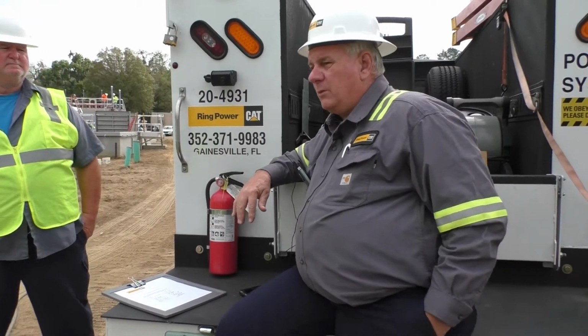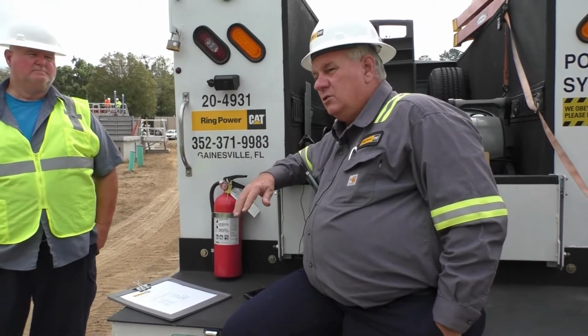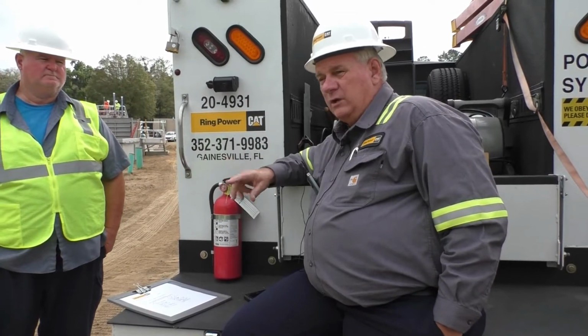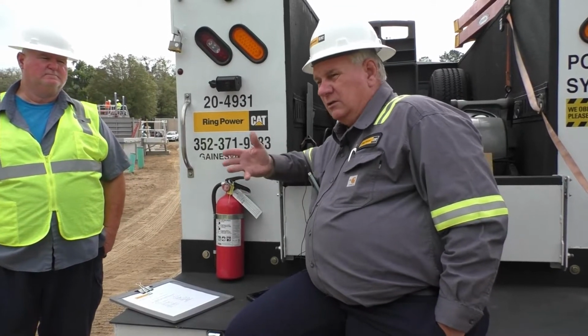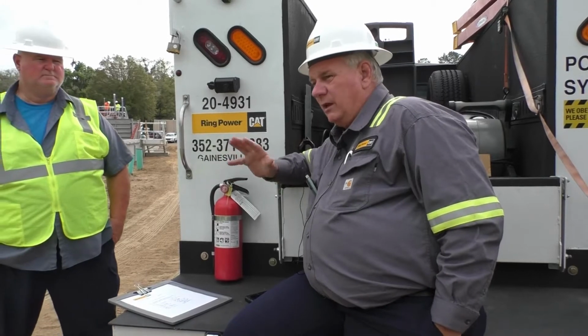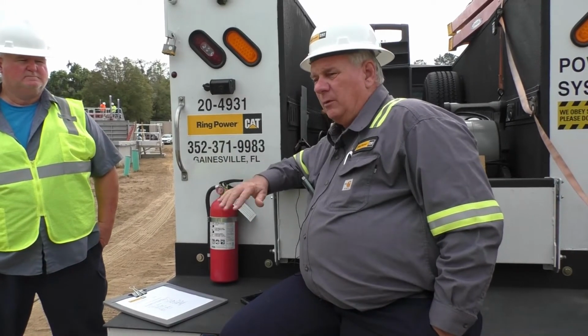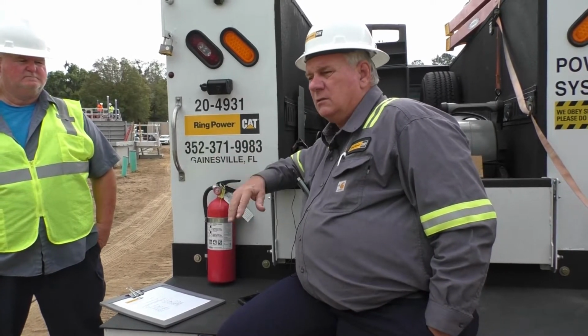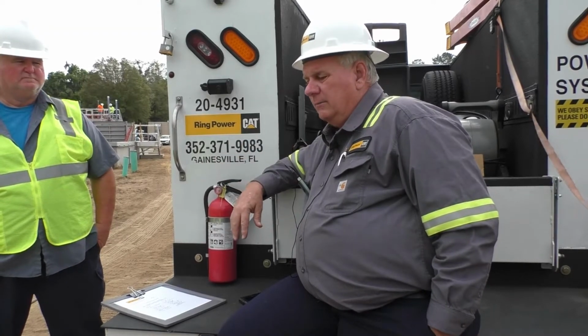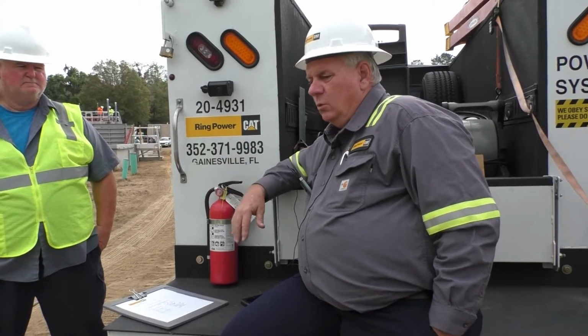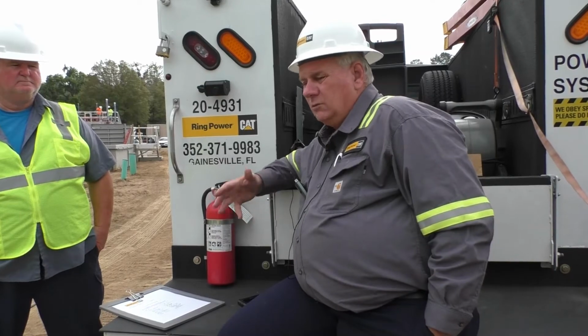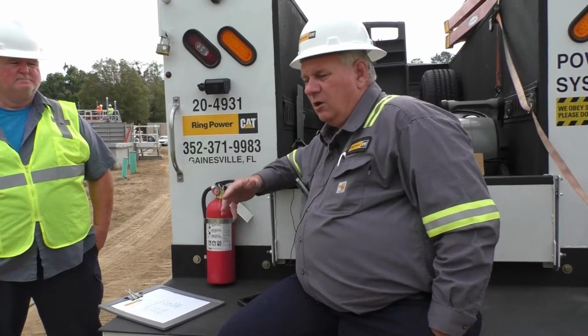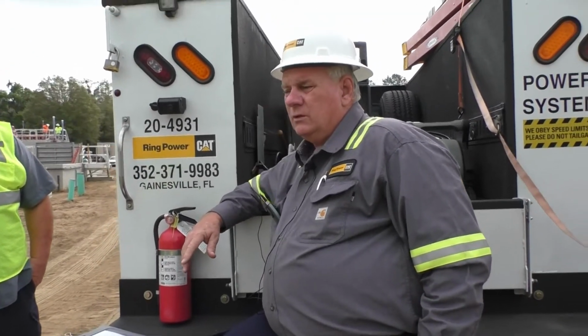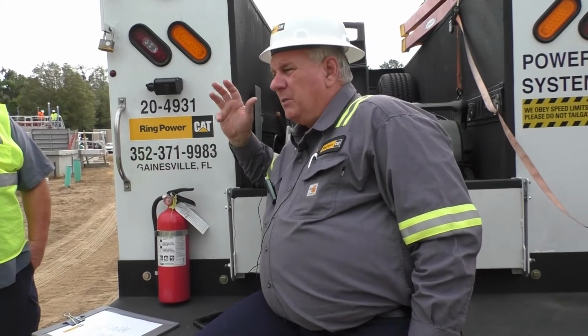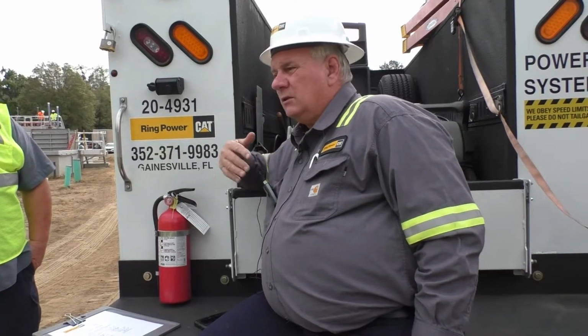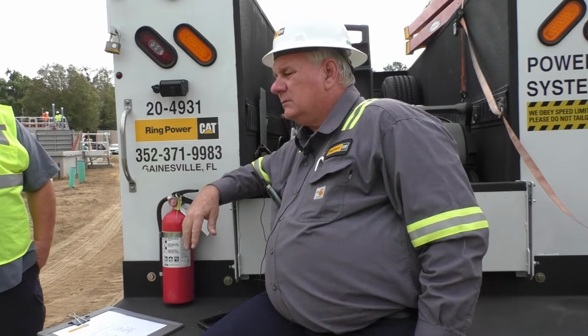There are 2 separate utility feeds to the transfer switches, so you could lose one and not the other, and be on one transfer switch and on normal power on the other. Just to mention that ahead, if you have something going on in your plant and you trip a main for some reason, that's what you'll see. The transfer switches will start and stop the generator automatically, like they all do. There are a couple of e-stops on this thing, one on the main panel, one on the inside wall. They'll both come up with the same exact alarm.